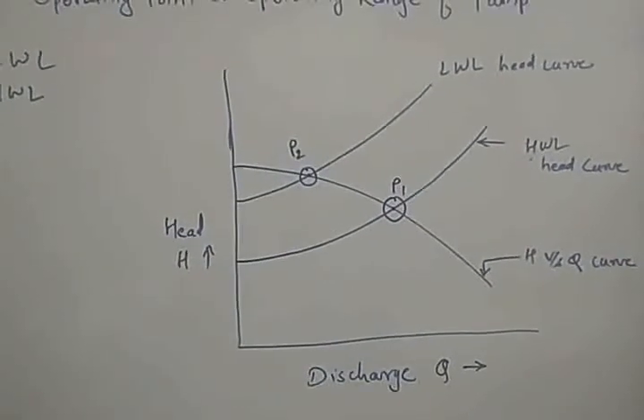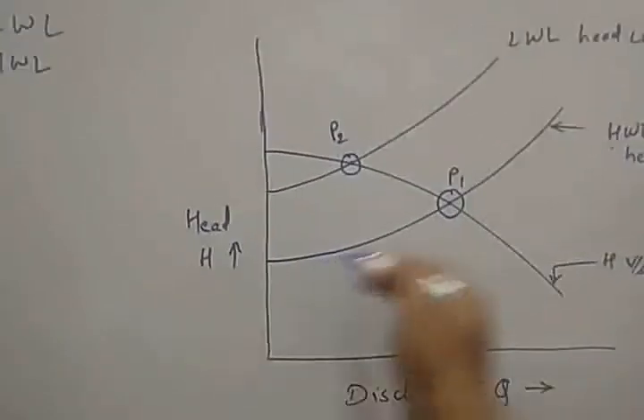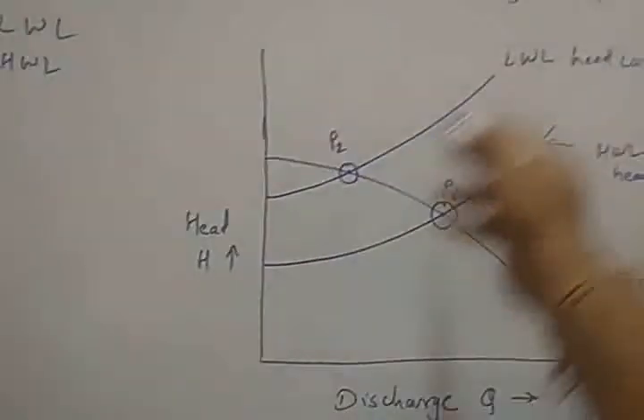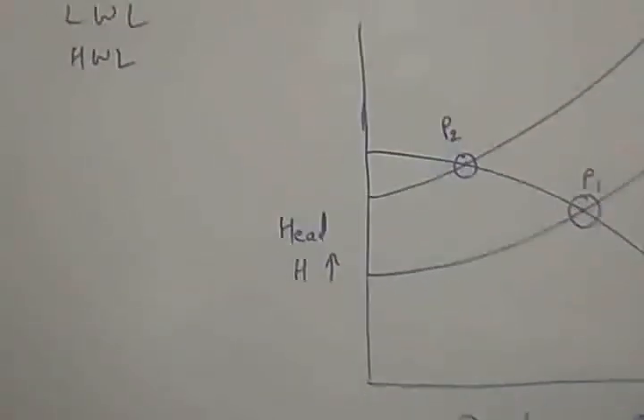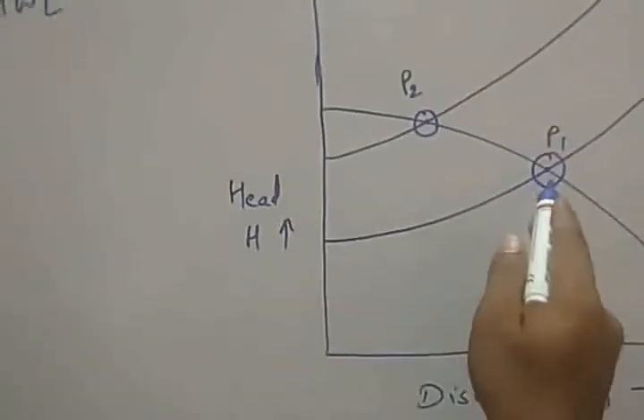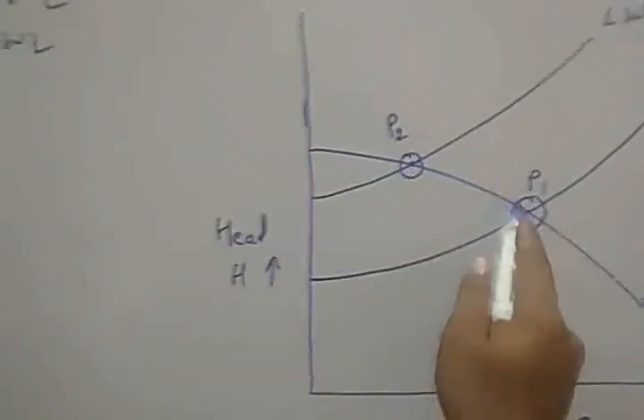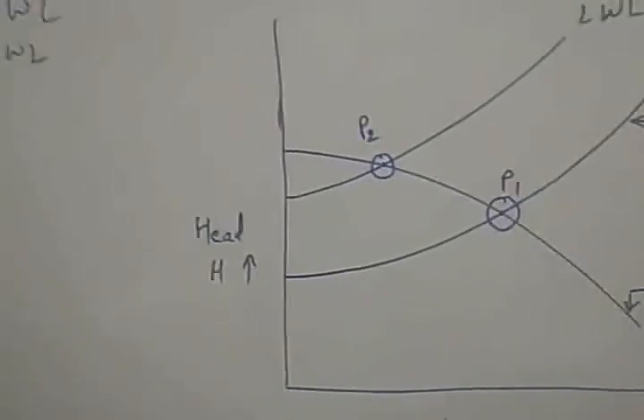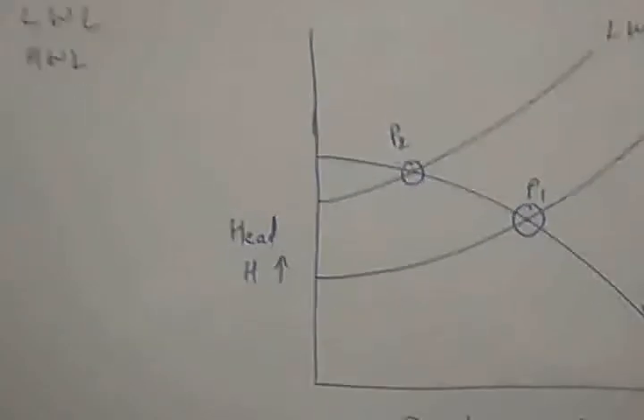This is the plot for the lower water level head curve and the higher water level head curve. The higher water level head curve and lower water head curve intersect the head-versus-discharge curve at points P1 and P2. This range from P1 to P2 is the operating range of the pump due to fluctuation in the water level or sump level.